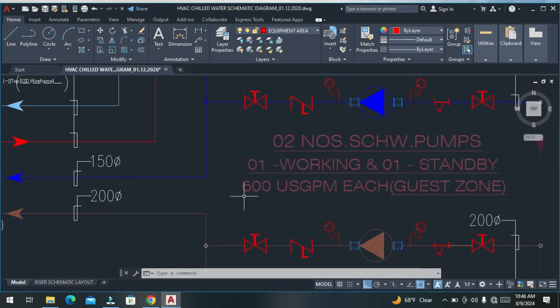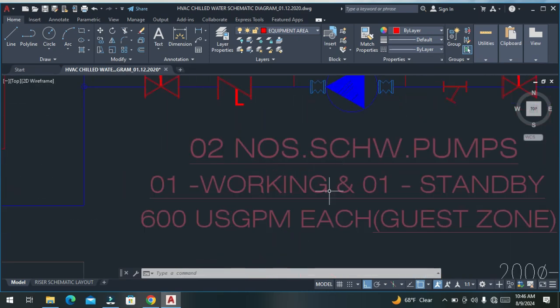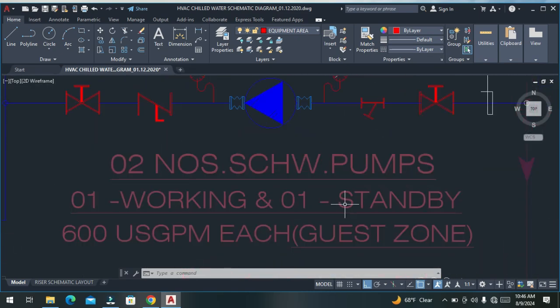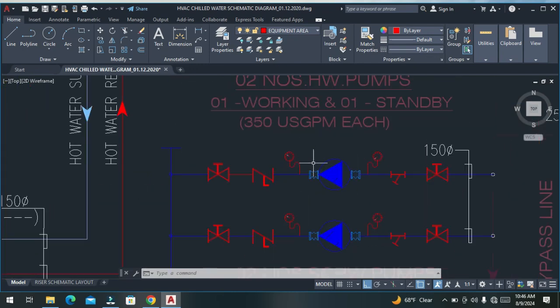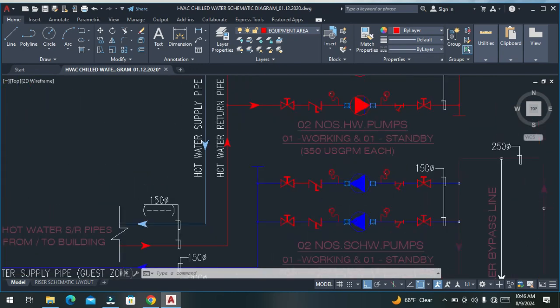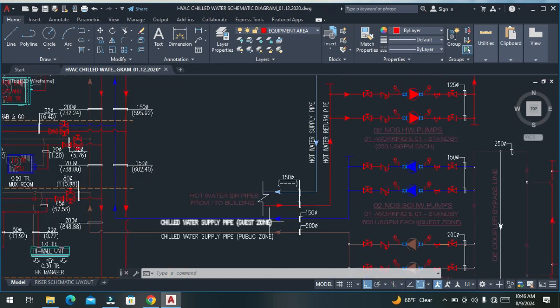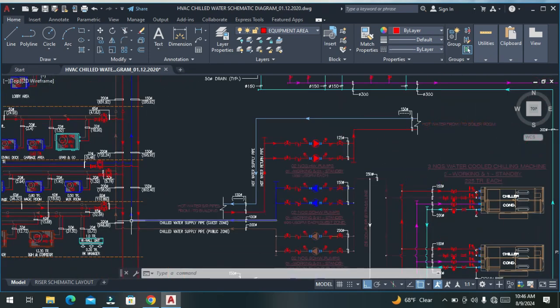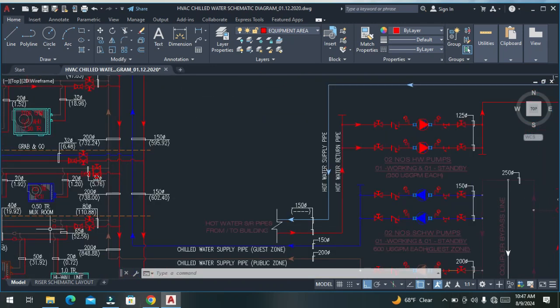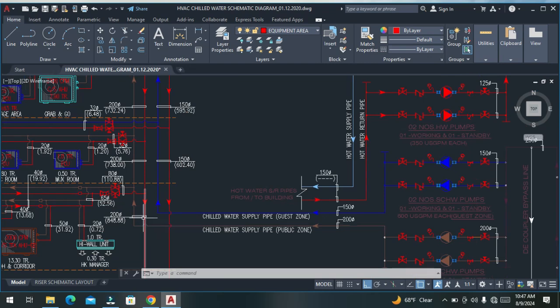Its pump capacity is 600 GPM, gallons per minute. One is working and another is standby. So if you trace this pipe, where will it go? If you look here, this is actually the supply line. Chilled water is taken from the evaporator output line with the help of this secondary pump, and then it will supply to the units.